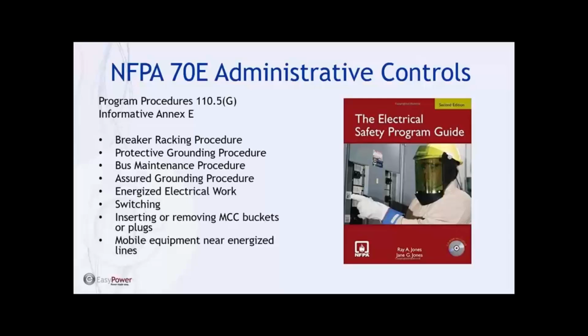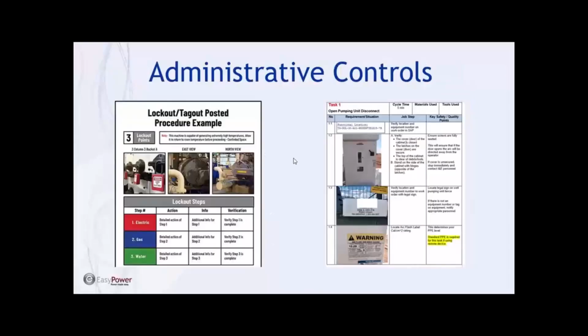By my estimation, what you look at are things that are higher risk: racking breakers, installing protective grounds, switching mobile equipment near energized lines, all these sorts of things. This is where you'd have a written or standardized work instruction in order to perform that work. If your employees follow the procedure as written, you'd certainly reduce the risk of arc flash, shock, electrocution, or exposure to other hazards.